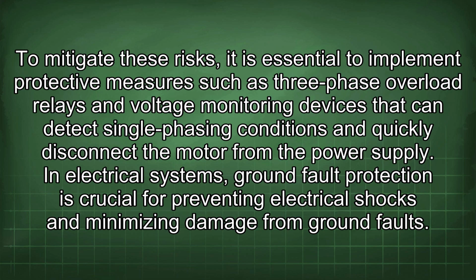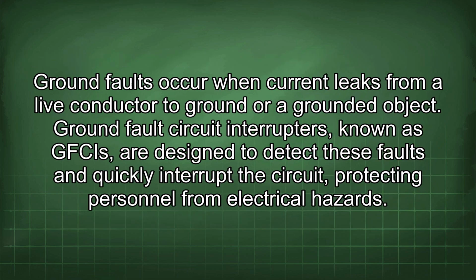In electrical systems, ground fault protection is crucial for preventing electrical shocks and minimizing damage from ground faults. Ground faults occur when current leaks from a live conductor to ground or a grounded object.